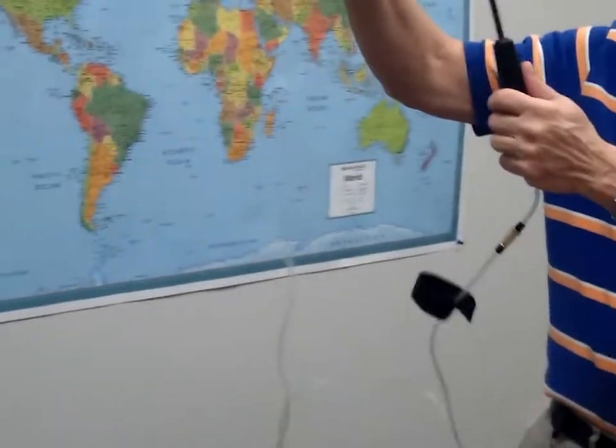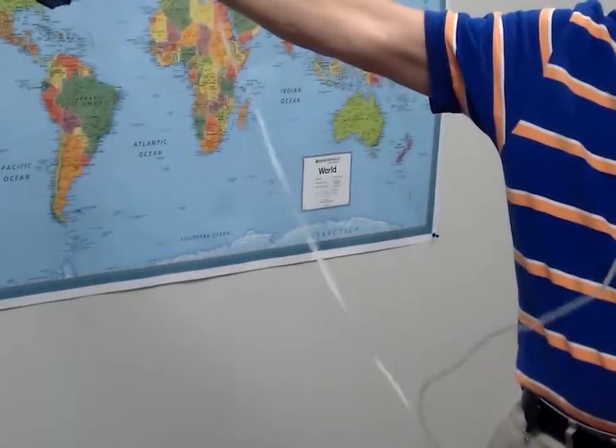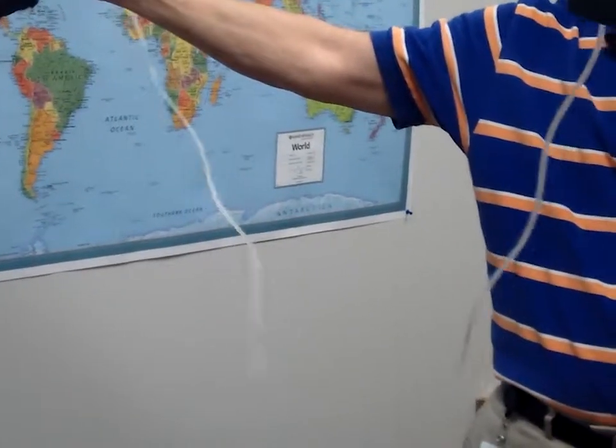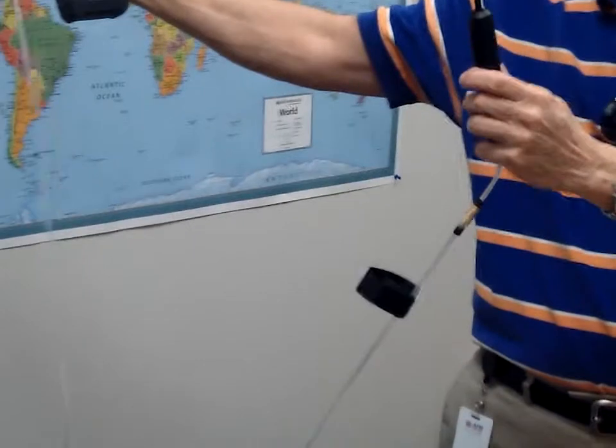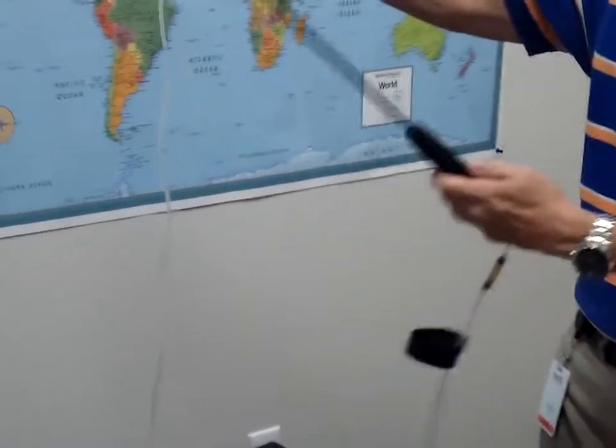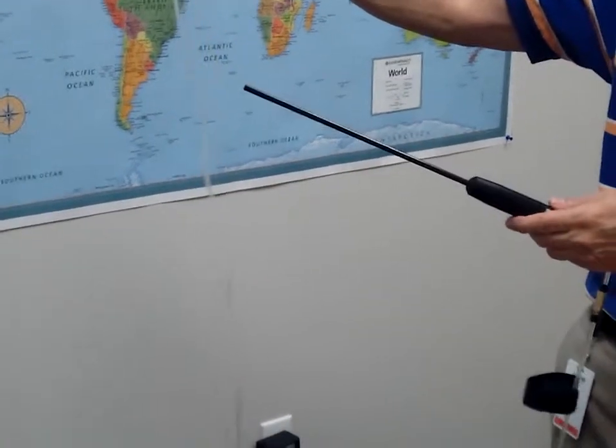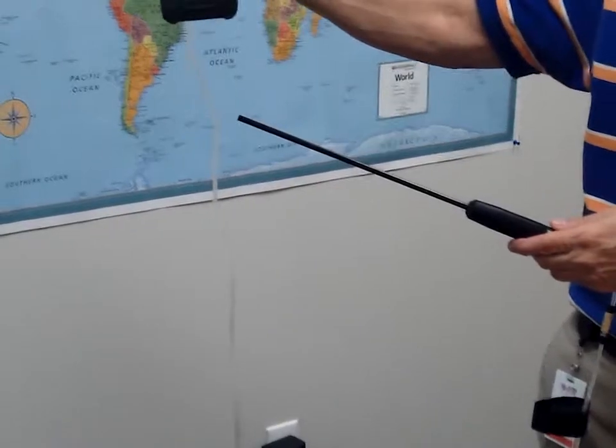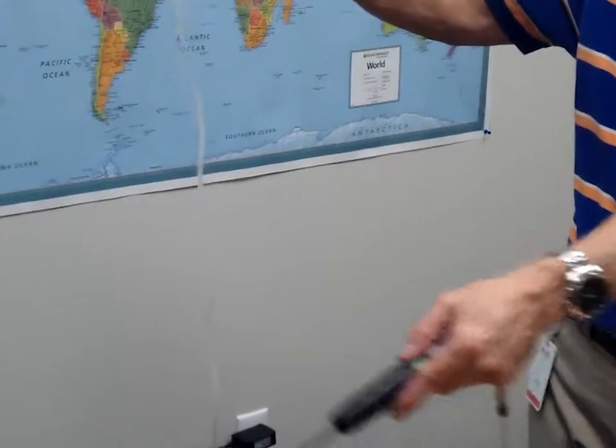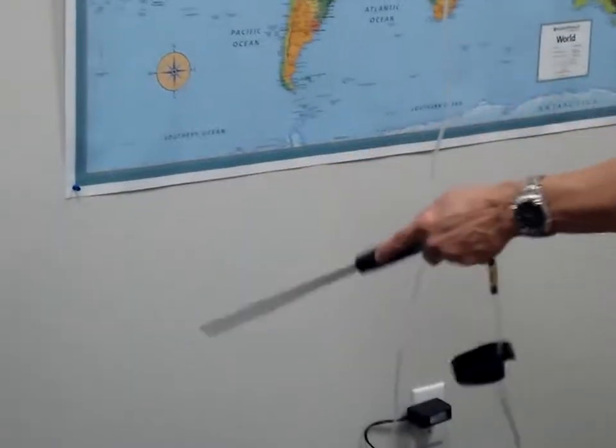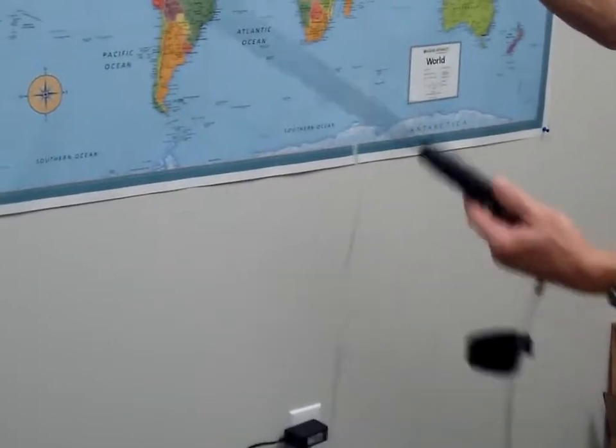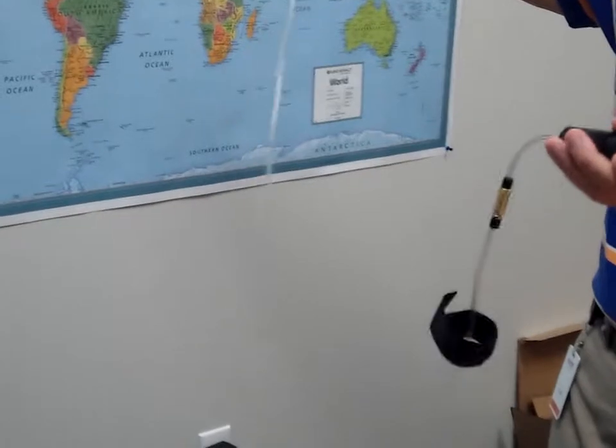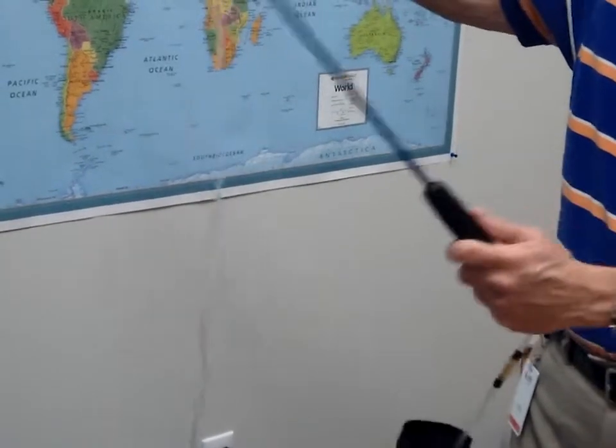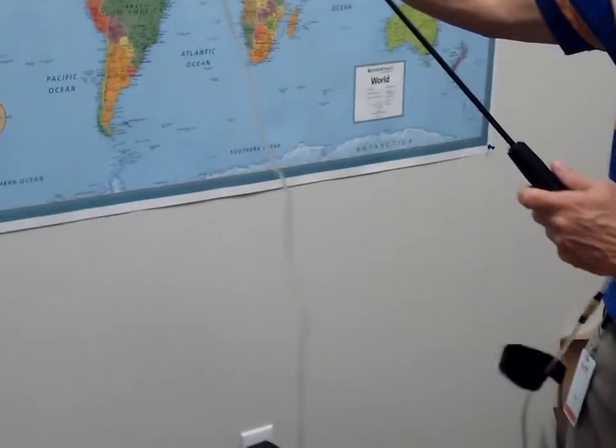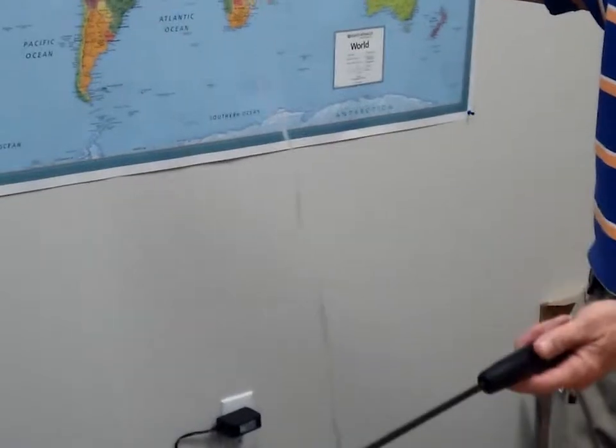At this point, you're drawing the air from here all the way into a 10-foot line, and then with about 1.5 feet of probe, which means that the air is having to travel through that tube. The standard rule of thumb is 1 foot per second. So whenever you're doing any kind of remote sampling like this, and if you're doing any kind of monitoring of flanges or pipes, you would want to make sure that you're giving it a full 12 seconds for that gas to get from the tip to the sensors on the unit.